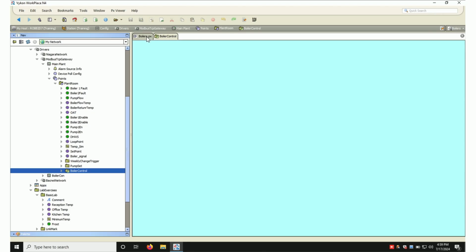So in this example here, the user account will be accessing the station space and be fully captured by the station security. Whereas in this example, they would be in the file space, and it does depend on how the security is set up. But as I previously explained, certain things just don't work in this type of view, and there's a security implication. So an engineer who knows Niagara well could potentially start to manipulate the path that they're in and start looking at files or going to places they're not meant to go to. So we're going to start to look at how to build this page up.